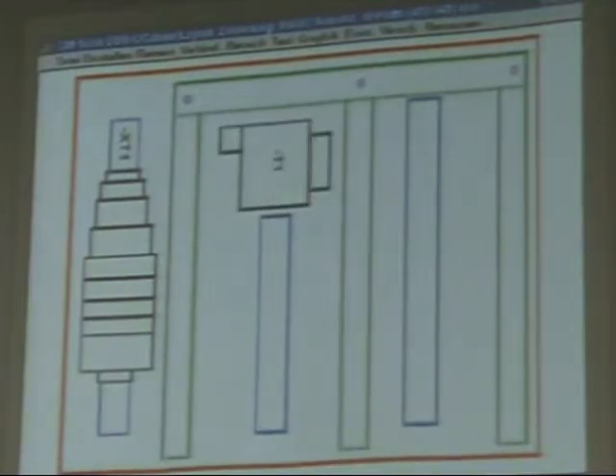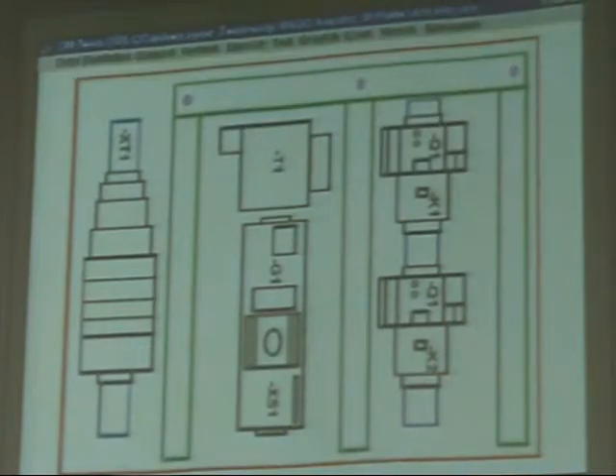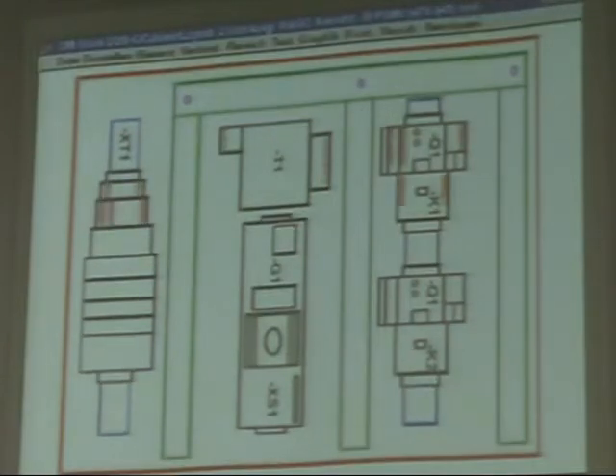Information from the schematic diagram is then used to generate the control panel layout and wiring. First, automatic and manual placement of parts onto the mounting plate is carried out. Automated checks necessary for the robotic wiring are performed automatically. These include a minimum distance check between components and cable ducts. An option for automatic placements of components onto standard mounts provides extremely rapid creation of the mounting back plate.